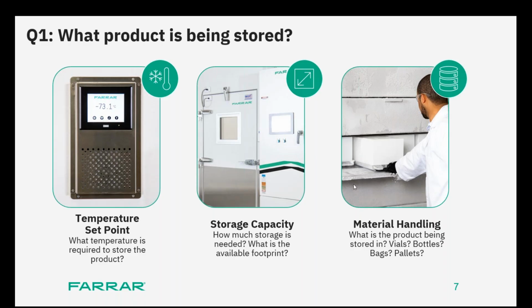Those are some key aspects of the people that will be going in and out of the chambers. And then we're also going to ask you questions like, is your product coming in on pallets? Are they coming in on carts? Are they going to be in bottles or bags? What is that method there? Is that material going to be water-like or something similar? Is the packaging going to be stainless steel, plastic, or glass? And how much of it will be in there per day? Are you bringing it in and out? What is its weight and what is its temperature? The temperature is excellent to know.